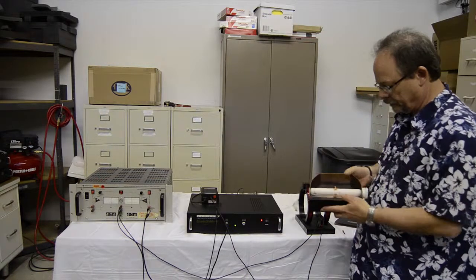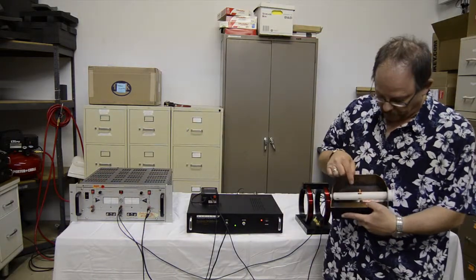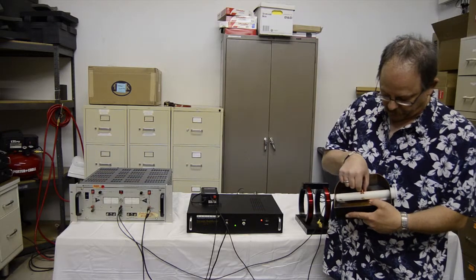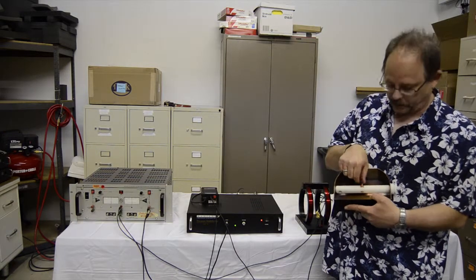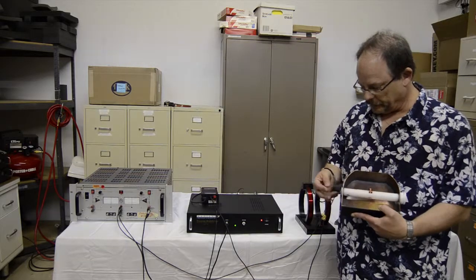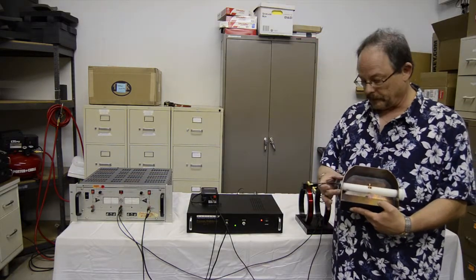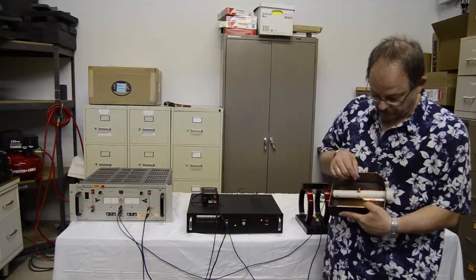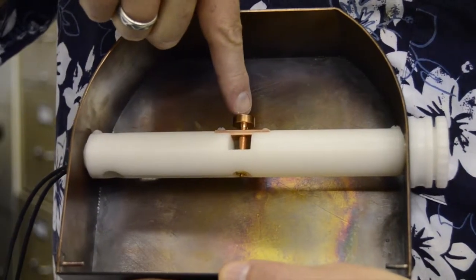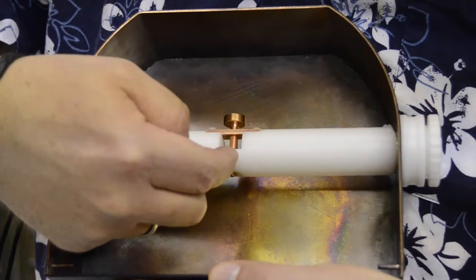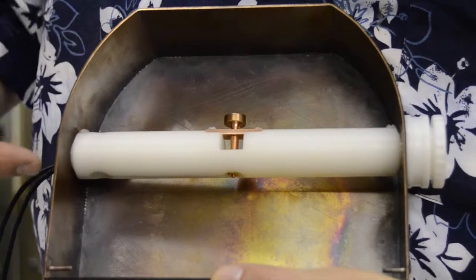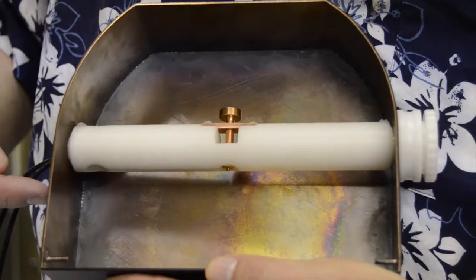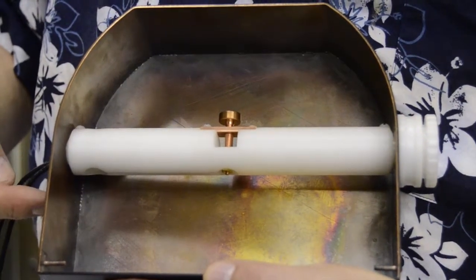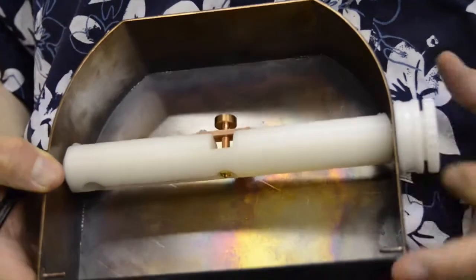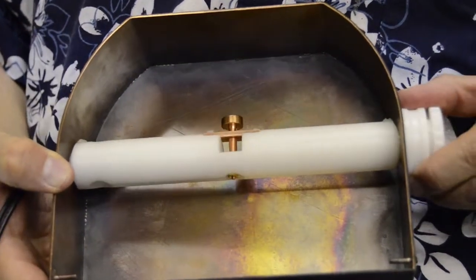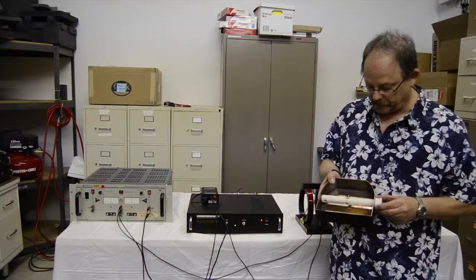This is a prototype. It's a little different from the one that we ship. Basically, this connector is spring-loaded in the one that we ship. Here, it's nut tightened, and the SMA connectors are mounted directly and are female on the shipped model. The sample gets inserted into the sample holder between the top electrode, which is the spring-loaded contact, and the bottom electrode, which is a fixed copper contact connected to the SMA cables. The sample can be oriented rotationally in any orientation that is necessary.